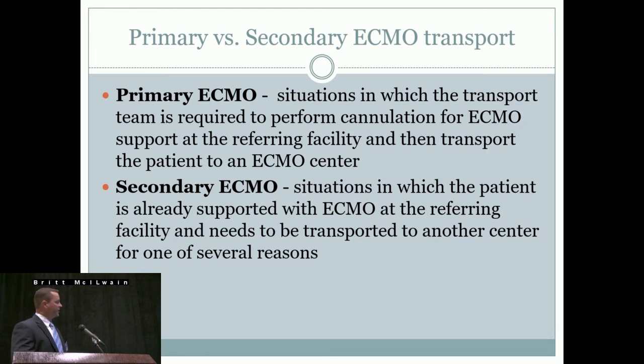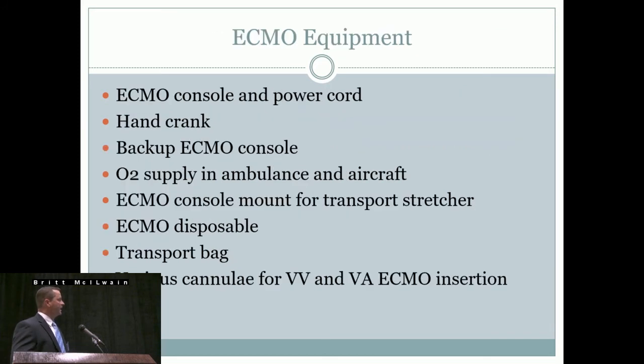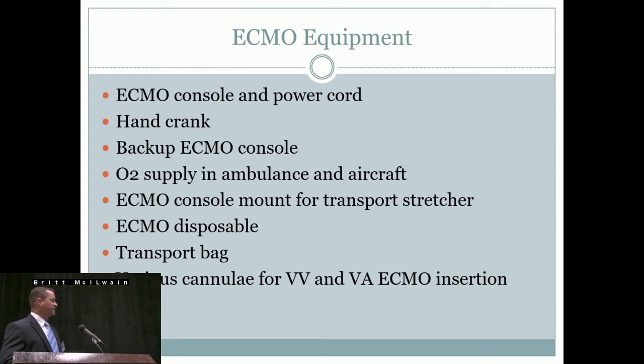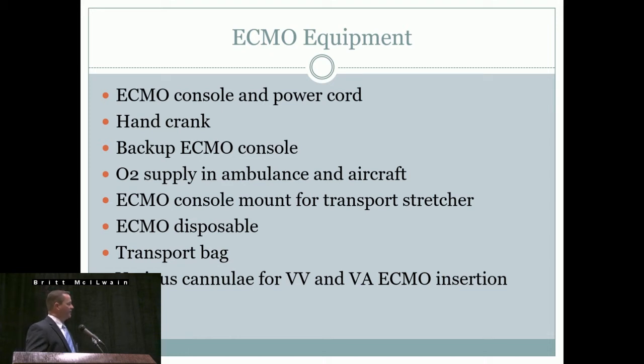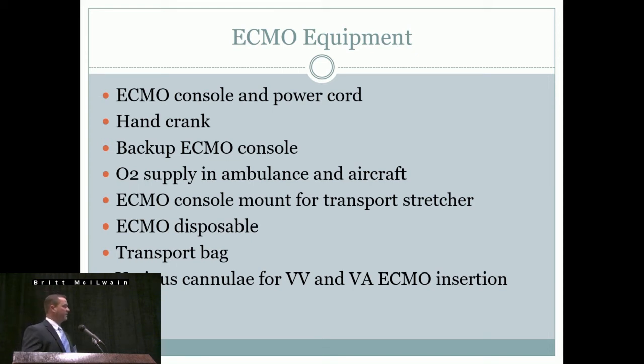Secondary ECMO transport involves picking up a patient who is already on ECMO and transporting them to your center — most of the time for bridge to transplant. Equipment needed includes your console, power cord, hand crank, backup console, O2 supply for both the ambulance and aircraft, mounts, disposables, transport bags with clamps, fluids, IV tubing, and various items the critical care transport team may not provide. You also need to think about whether to bring VV and VA cannulas, since you may start with one modality and end up needing several.